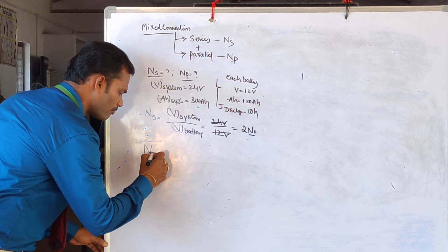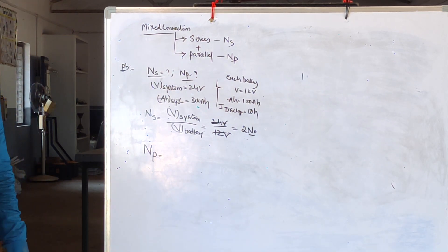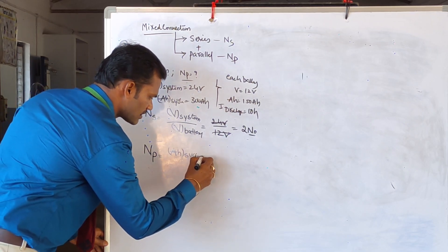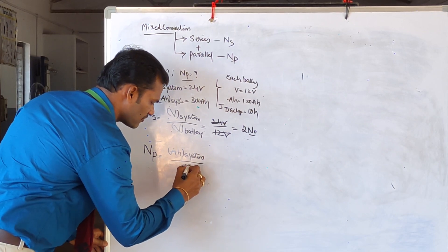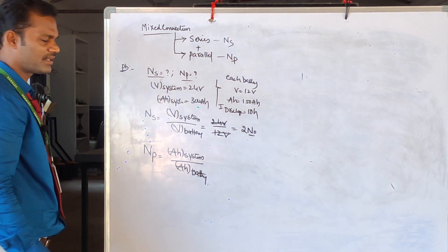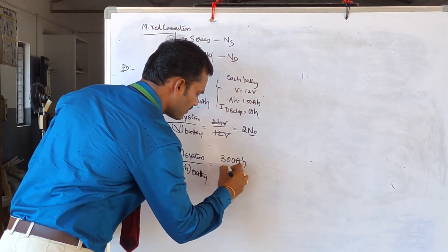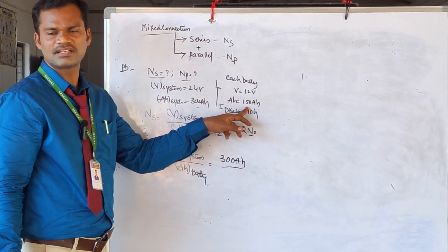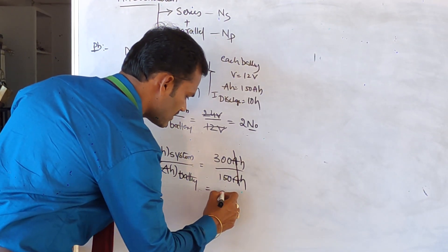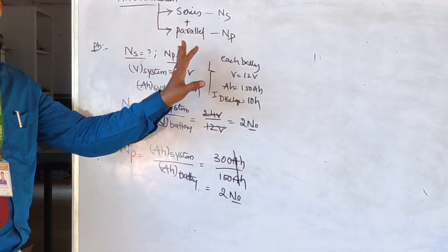Next, we need to calculate the number of batteries to be connected in parallel connection. In a parallel connection, AH capacity is increased. The formula is: AH capacity of the system divided by AH capacity of the individual battery. That is 300 AH divided by 150 AH — the AH units cancel, giving us 2 batteries to be connected in parallel.